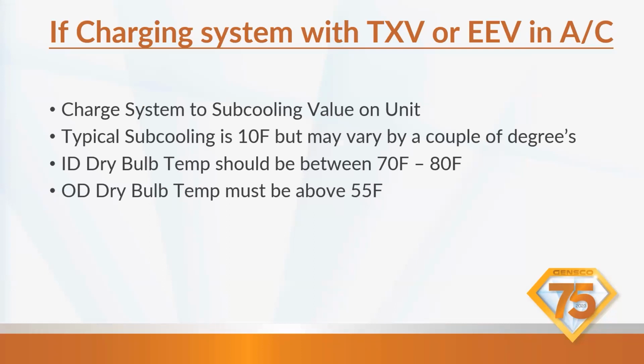If charging a system with a TXV or EEV in air conditioning, we're going to charge the system to the subcooling value on the unit. Typical subcooling is about 10 degrees Fahrenheit, but it may vary by a couple of degrees. So always check your data plate. Your indoor dry bulb should be between 70 and 80 degrees. This is for cooling. Outdoor dry bulb temperature must be above 55 for cooling.